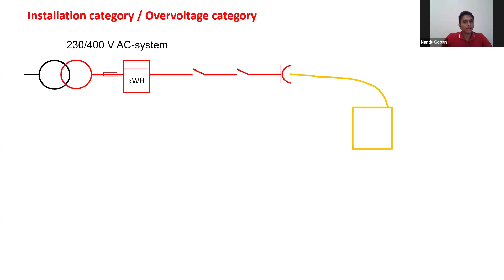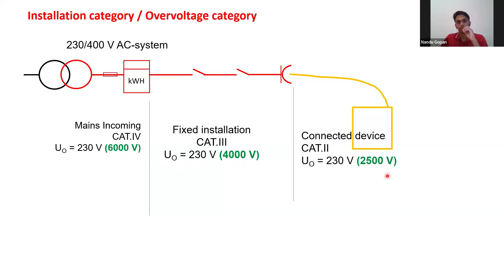I think I have only 3-4 slides, so I'll go a little fast. This is something called overvoltage category. Every equipment is categorized into category 4, 3, 2. The transformer is category 4, the fixed installation is category 3, and connected equipment is category 2. They are tested for impulse voltages of 6 kV, 4 kV, and 2.5 kV that they can withstand.